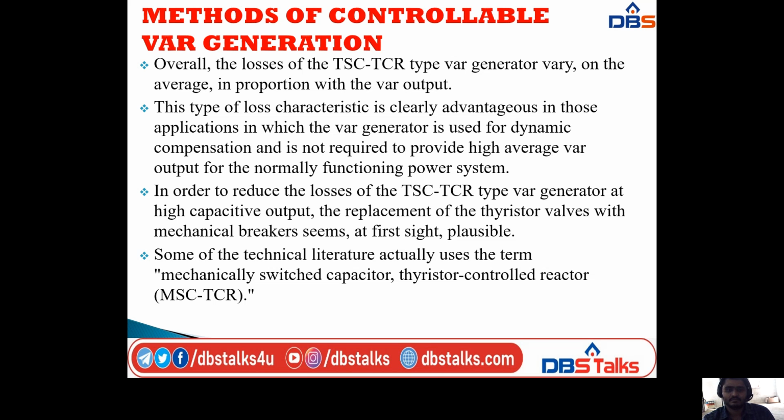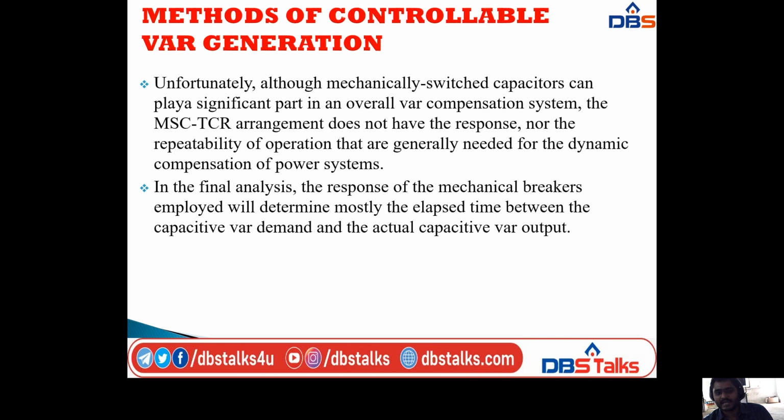Okay. So unfortunately, although mechanically switched capacitors, that is MSCs, can play a significant part in an overall VAR compensation system, the MSC-TCR arrangement does not have the response nor the repeatability of operation that are absolutely needed for the dynamic compensation of power systems. In the final analysis, the response of the mechanical breakers employed will determine mostly the elapsed time between the capacitor VAR demand and the actual capacitor VAR output. So this is the concept for the methods of controllable VAR operation.